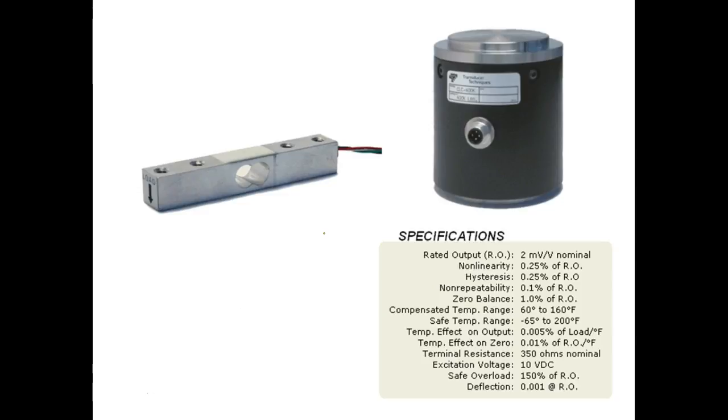And then the scales will be rated a certain way. We had them rated in pounds. We had 8,000 pound scales, which would be 4 tons. On a railroad scale, you put 4 of them under there, at least 4, maybe 6. You'd always use them in pairs. Does that make sense? The weight was distributed out above them, and then they were summed together.